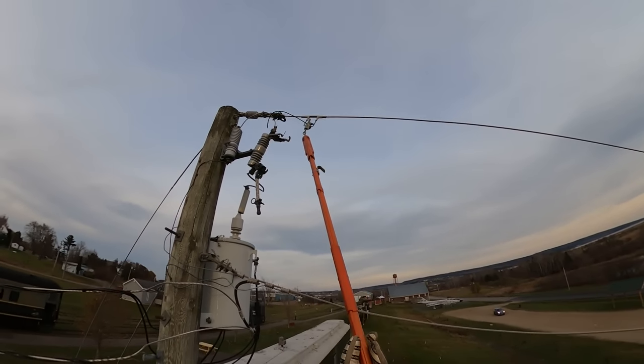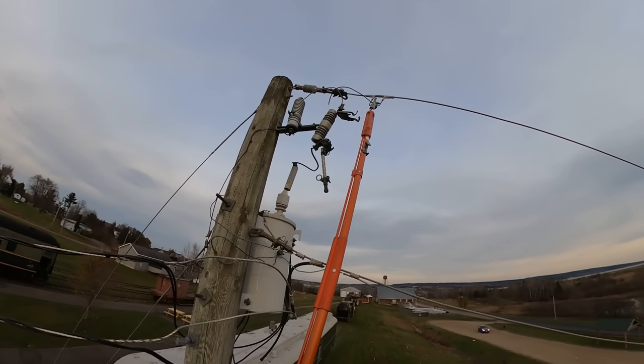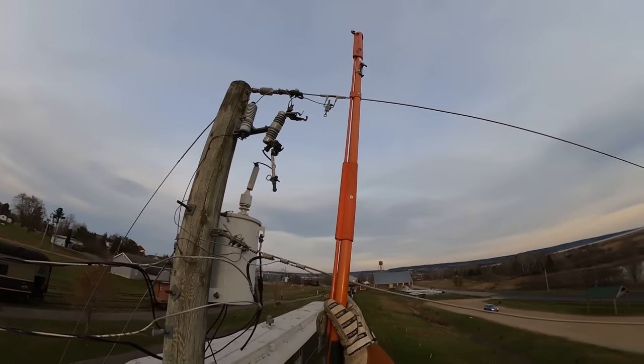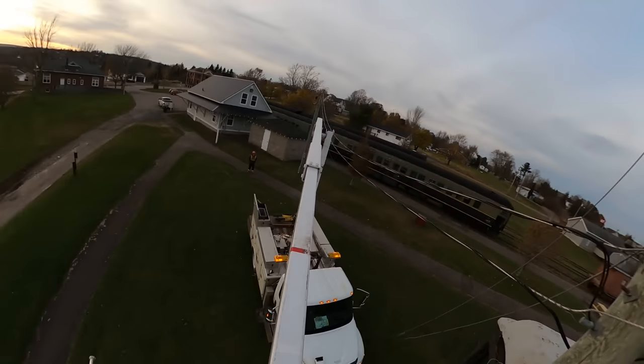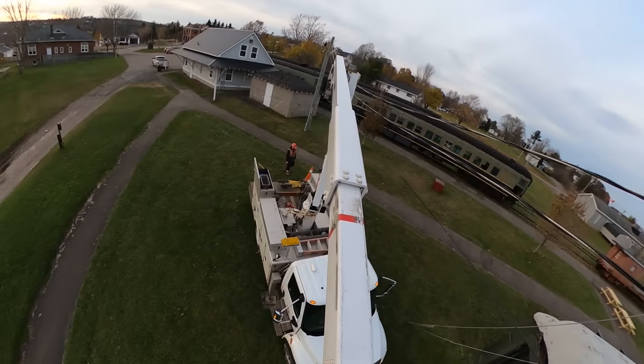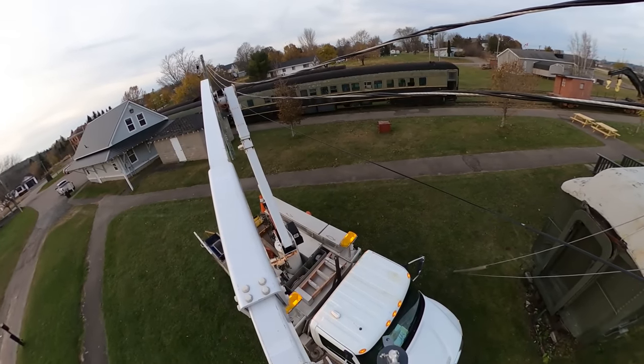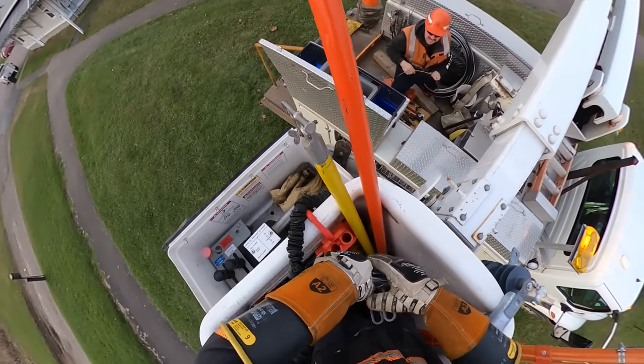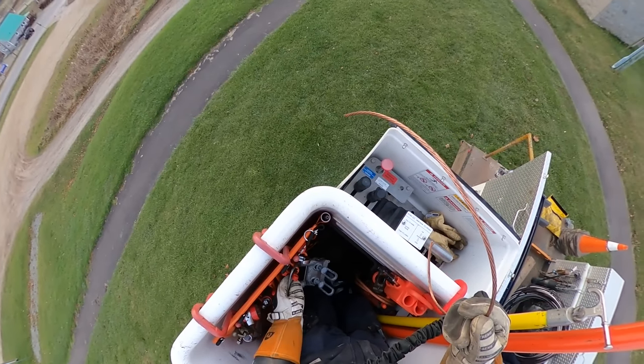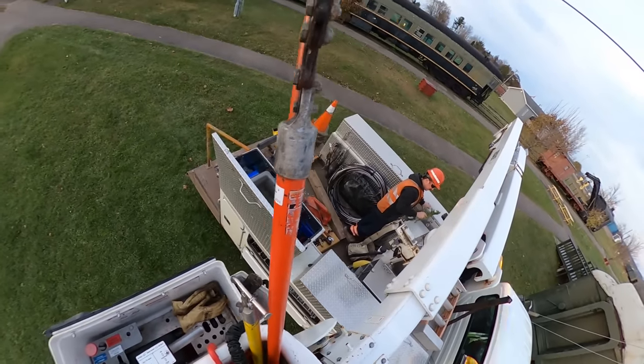We don't want that wire bouncing against that cutout trying to pick up load, which I'm assuming it will bounce around a little bit as we get going. So we'll put our grab-all on and try to haul it away from the top of the cutout. Even though the cutout is isolated now, there is still one hazard: the lightning arrester. That lead isn't long enough to hit the cutout bracket — which would be very bad — but that's a concern. So I'm going to get some hotline cutters and cut that lead right off. Even though that lightning arrester is designed to take high voltage, I don't want to be repeatedly energizing it with that lead bouncing off it.